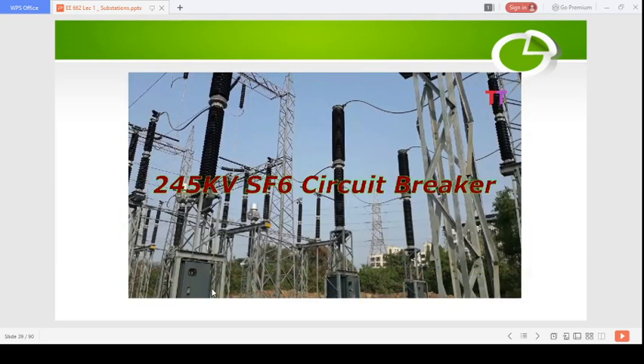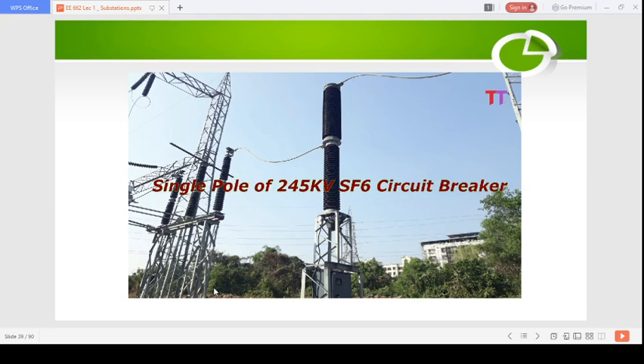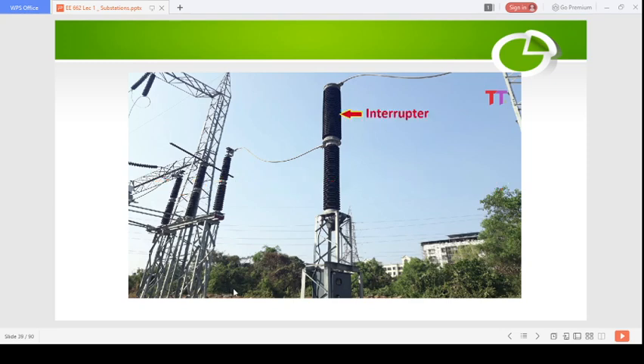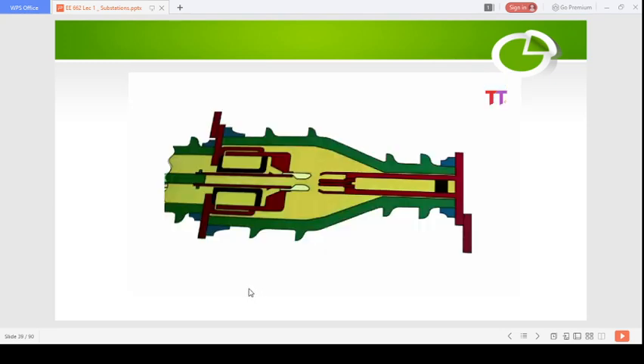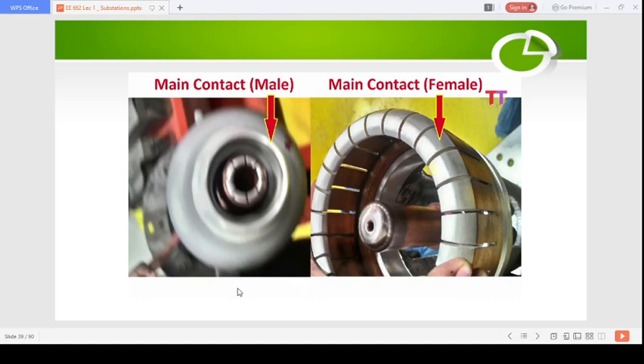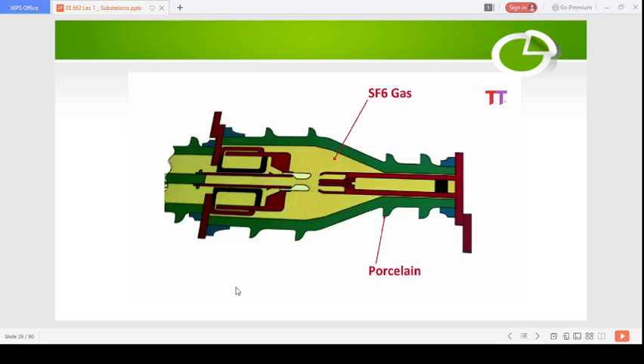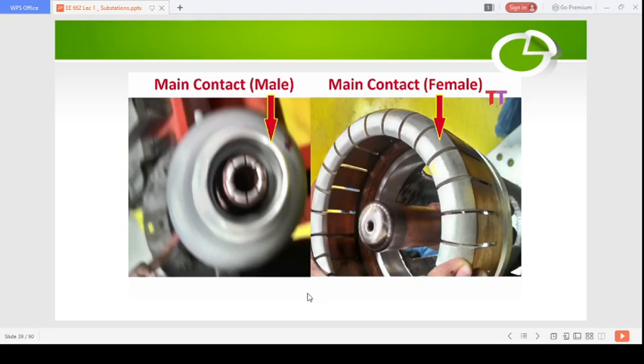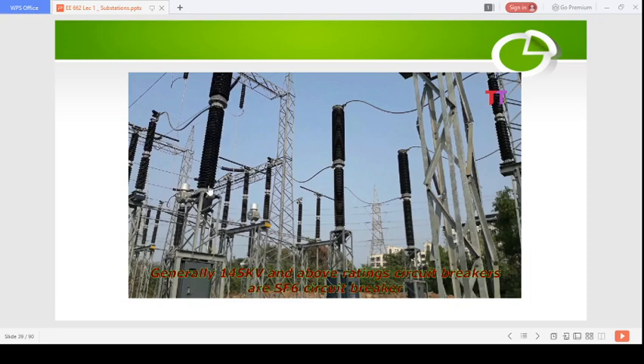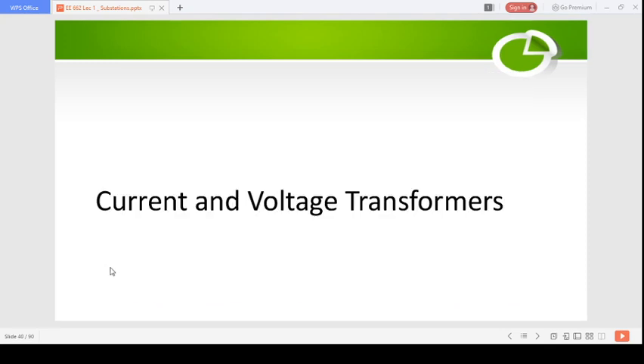This is a 220 kV SF6 circuit breaker, and this is a single pole of two main components. The longitudinal section of the interrupter. If we look close, this is the side porcelain housing. We can see two main contacts. This one is the male contact which is moving, and this other one is the female contact which is fixed. This is how these two contacts look like. If we look closely, we get the actual feeling of what's inside this circuit breaker. Typically what you will see is something like this. But everything is inside, so you will see what the things inside are in this video.